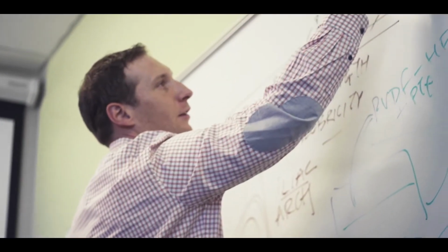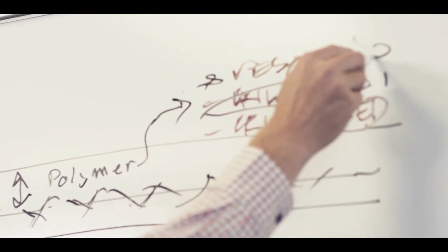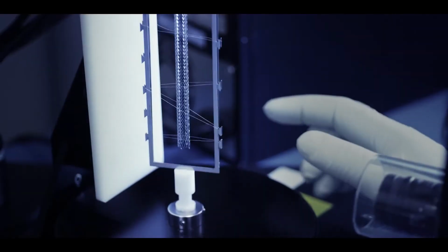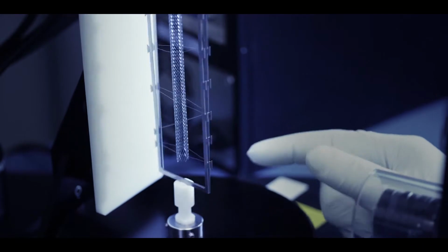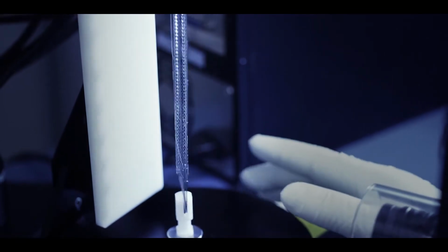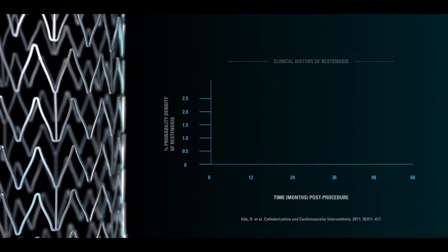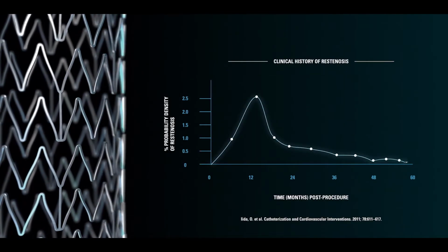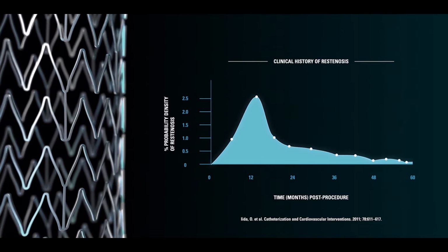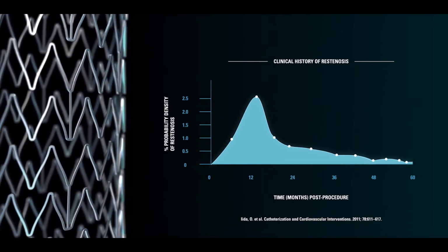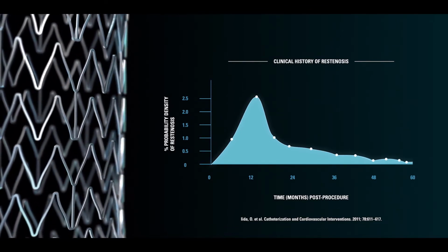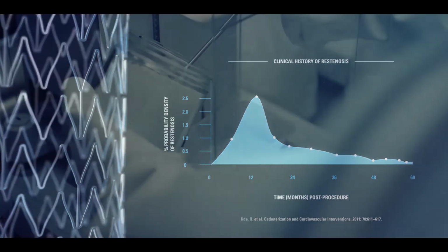To better understand how and when release should happen, Boston Scientific R&D studied current and competitive drug-coated technologies. They looked at studies of how the SFA healed and how well these drug treatments matched the natural response of the dynamic human body. One specific focus was the restenotic cascade. The restenosis timing in the SFA is longer than other anatomies, which meant Boston Scientific engineers had to design for an elution curve that released more drug over a longer period of time.